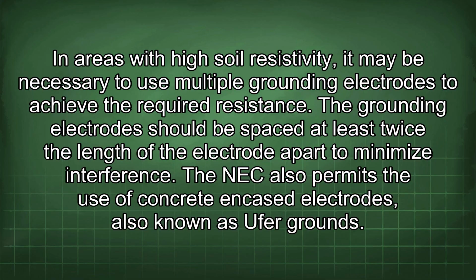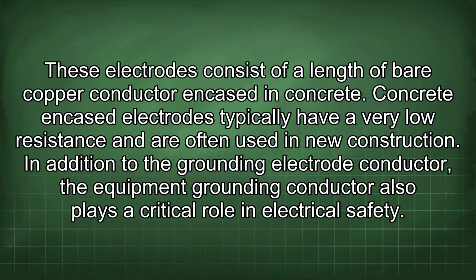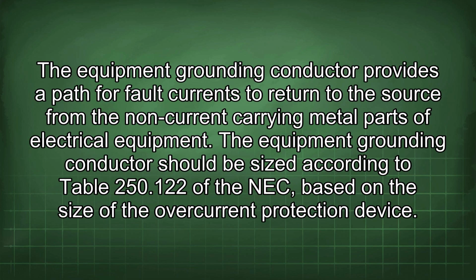The NEC also permits the use of concrete-encased electrodes, also known as Ufer grounds. These electrodes consist of a length of bare copper conductor encased in concrete. Concrete-encased electrodes typically have a very low resistance and are often used in new construction. In addition to the grounding electrode conductor, the equipment grounding conductor also plays a critical role in electrical safety. The equipment grounding conductor provides a path for fault currents to return to the source from the non-current carrying metal parts of electrical equipment.